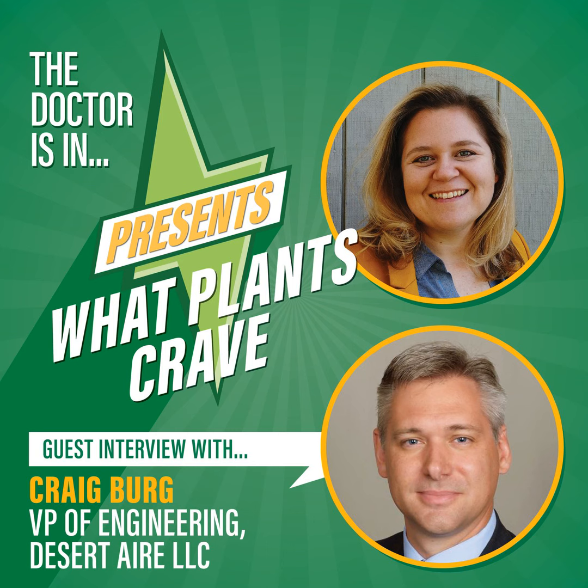Is the dynamic nature of these grow rooms a part of the issue with how the expansion valve is responding? I'm just trying to understand, what is so special about indoor plant environments? And we started the conversation with, they're very dynamic. We have photo period, dark period. We have the transition period. We haven't even talked about that yet, right? Where the equipment is trying to catch up with the load, and vice versa. Is some of that dynamic nature sort of pushing this equipment to its limit, or are some of these components unable to respond quick enough to the change in what's happening in the environment, so that the expansion valve stays open because it was in one steady state before the dynamic state created a new load that, oh my God, it needs to close? Is that part of what's going on specifically with this application?